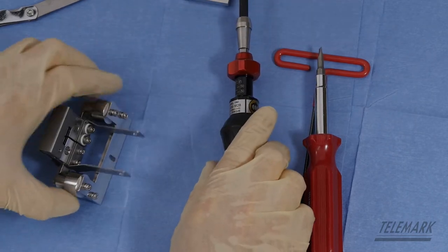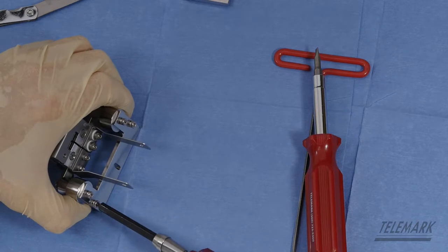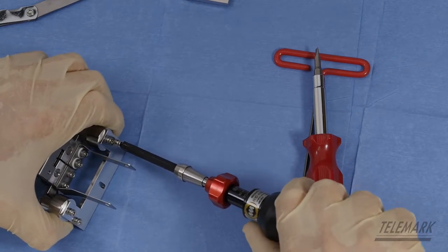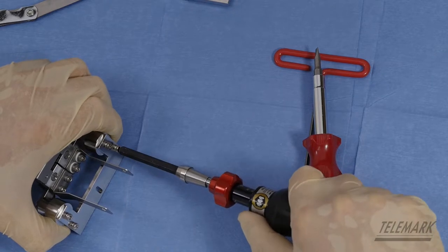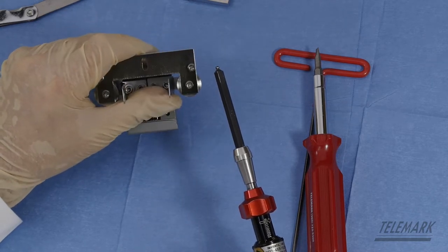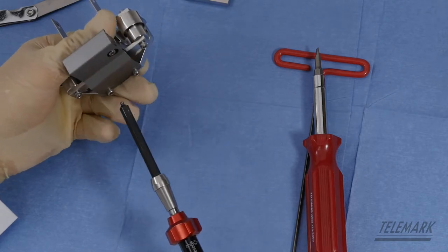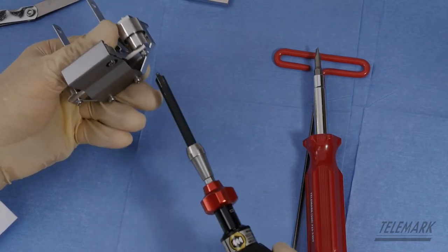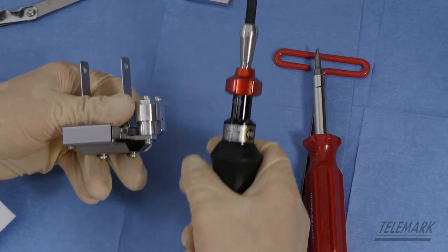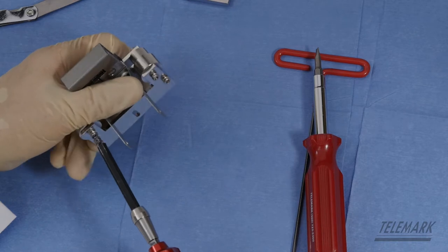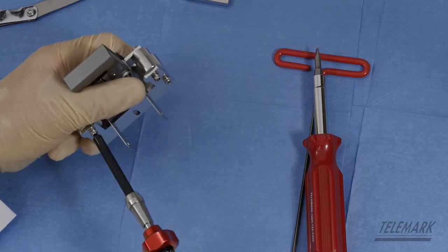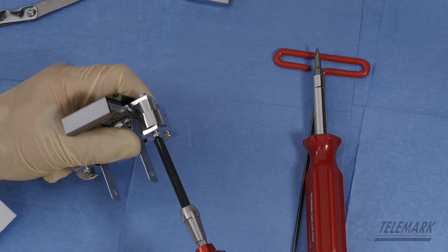Move that off to the side. Grab your torque wrench and put your thumb in there. You want to push up on the HV shields and down on the mount, then lock that down. Roll it around, put your thumb across the bus bars, hold the mount, and force the bus bars down. This helps square everything up. This is kind of a process because nothing wants to lock down due to the insulator shields. Snug them up a little bit, then push your thumb across the bus bars again with fingers on the mount. Start rolling that around and snug it back up.